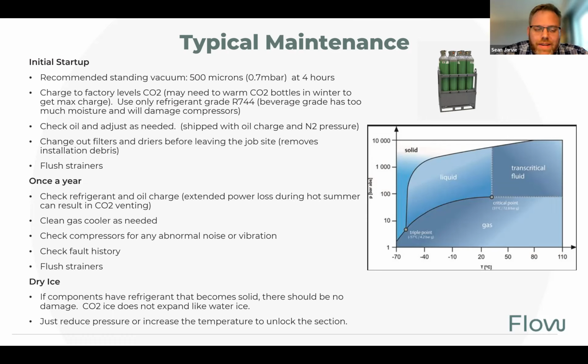And again, we want to make sure we check for any debris, make sure the coils are clean on the gas cooler, make sure there's no unusual faults, although your controller will be reporting into the BMS and alarming as we go. And again, flush those strainers because who knows what they found in there. I once found a dead pigeon inside one. That was an interesting find.